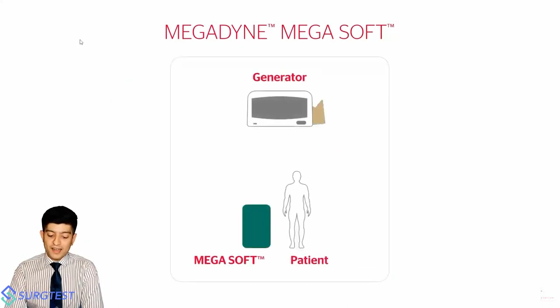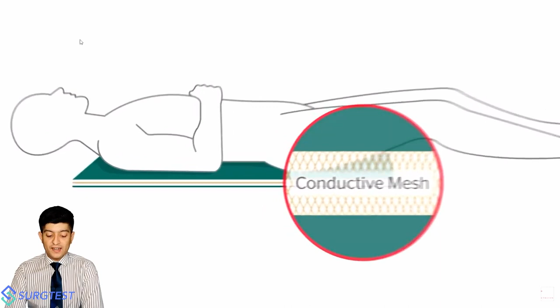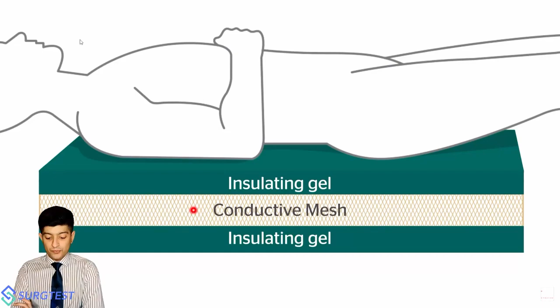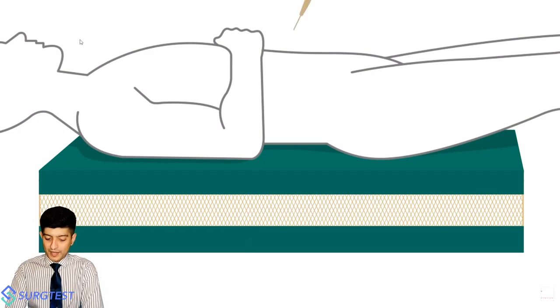Instead, you have these patient side pads, which are large capacitors. These pads are created with an insulating material on the patient side as well as on the OT table side, with a conductive mesh within the center. It is within this mesh that a lot of the electrical conduction eventually happens. When you apply voltage across the patient at this point in time, because there is an insulating pad, technically there is no flow of electrons from the cautery pen to this dispersive electrode that you're seeing on screen.